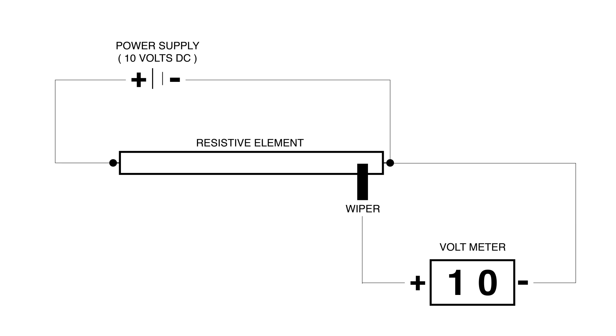The full-scale output voltage is equivalent to the excitation voltage. For example, an excitation voltage of 10 volts DC would produce an output of 0 to 10 volts DC.